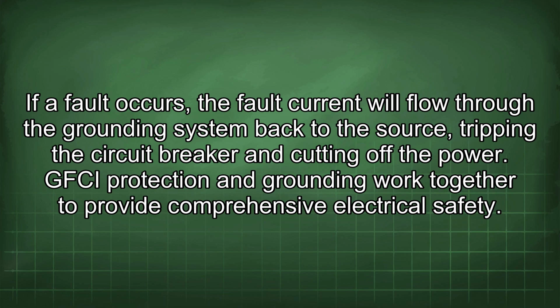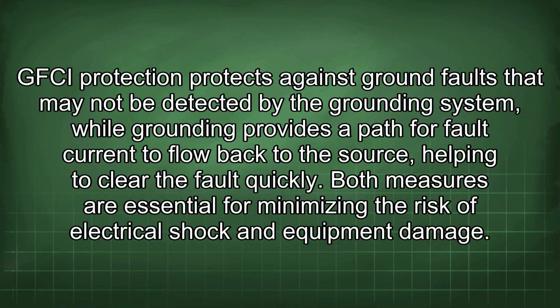GFCI protection and grounding work together to provide comprehensive electrical safety. GFCI protection protects against ground faults that may not be detected by the grounding system, while grounding provides a path for fault current to flow back to the source, helping to clear the fault quickly. Both measures are essential for minimizing the risk of electrical shock and equipment damage.